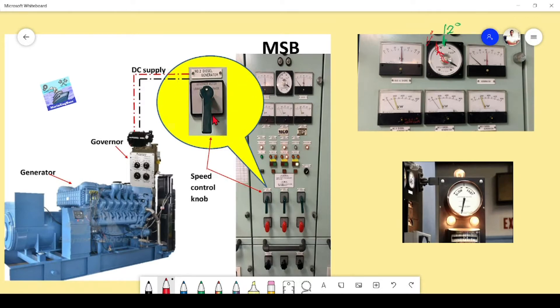Here is the enlarged view. What will happen once we turn this switch clockwise or anti-clockwise: there is an electrical signal fed into the generator which is outside in the control panel room. The generator governor at the top has a DC motor, so this DC motor will get the supply and it will compress the spring of the flyweight mechanism which is in the governor.